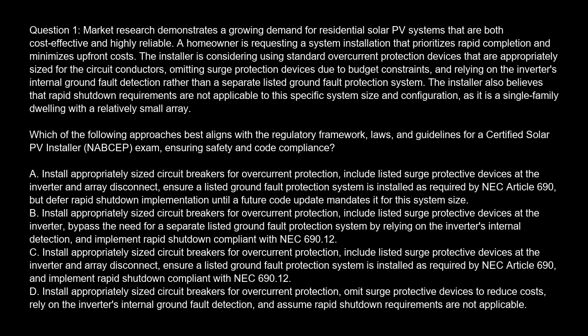Option A. Install appropriately sized circuit breakers for overcurrent protection. Include listed surge protective devices at the inverter and array disconnect. Ensure a listed ground fault protection system is installed as required by NEC Article 690, but defer rapid shutdown implementation until a future code update mandates it for this system size.